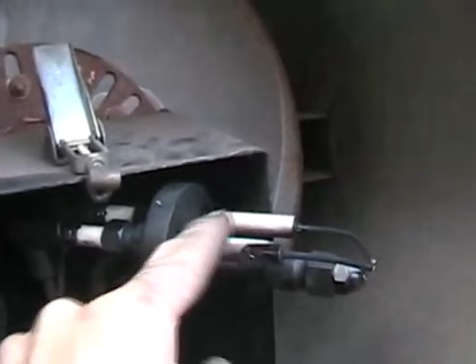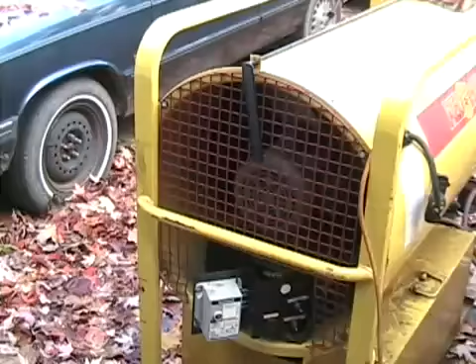These two white bars are ceramic insulators, like on a spark plug. These are your two electrodes. The high voltage spark jumps between to keep the flame always going. And just two high tension spark plug wires going to it. And this is the other side of your high voltage transformer. Here we have a safety thermostat in case for some reason the exhaust is blocked or the fire backwashes and comes into the combustion box, so it doesn't catch everything on fire and destroy it. This thermostat shuts the unit down if it gets hot. Then we have a photovoltaic cell, and this cell senses light. And I'll explain how that works in a moment.